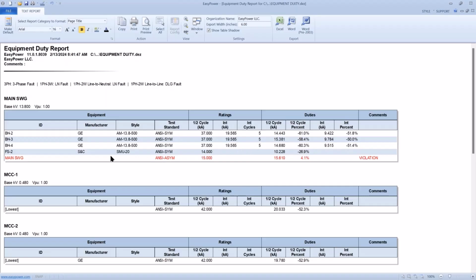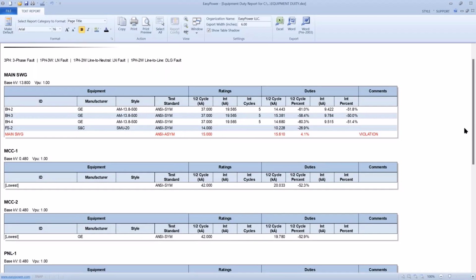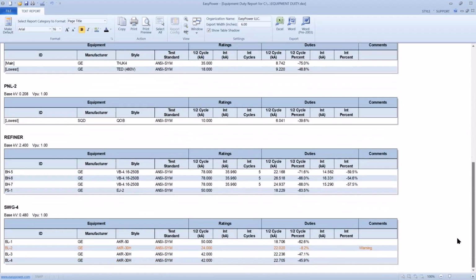But the bus work itself, the way I set the model up, I had a rating of 15,000 amps, and that's being exceeded during a worst case fault. So this is something that needs to be addressed, whether it's a data entry problem or something that's been in place for 25 years and nobody caught it. It needs to be discussed. And then we see that everything else is in good shape until we get down to that main bus, and I see BL2 is rated for 24,000 amps, and in a worst case, it's going to be hit with 22,000, which means it's still compliant, but it's inside that threshold.